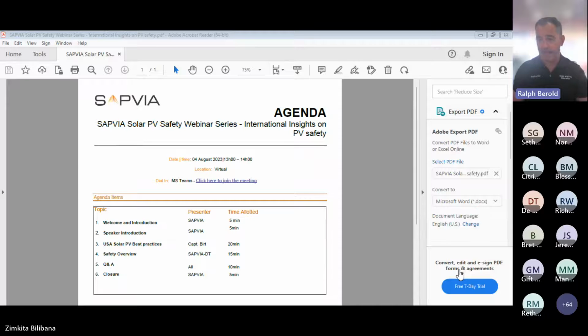Then how do you connect the panels together? Because that's the problem with high voltage DC and MC4 connectors. The number one fire risk. That's what happened on the Amazon build. They said, okay, now we have 230, 50 hertz. Does 230, 50 hertz cause an arc fault? No, because when we put it in the lab, there's nothing pushing the arc. So it goes to zero. So what we're looking at is not 600 volts pushing an arc. So if there is damage in the cable, it goes to zero and it shuts off. So we said, okay, you can get rid of arc fault at the panel level, where we've seen hundreds of fires, by converting it to 230, 50 hertz.